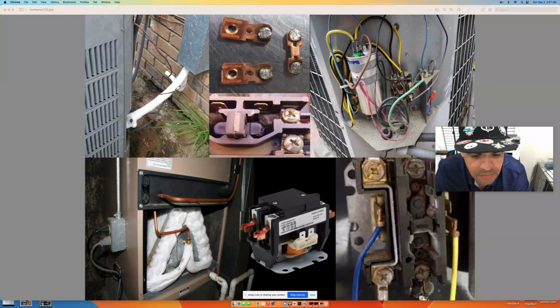Okay, so pretty much here, if you notice, when you see that frozen coil, that just means that your contactor here, if you look at it, the contacts can get stuck. Now, believe it or not, this problem does happen, but not that often. It does happen sometimes. It's not your main reason why a unit will freeze up, but it does happen from time to time. I haven't had too many. I think I only had maybe one stuck contactor this year in summertime, and the majority were actually capacitors. But it's still good to know this.